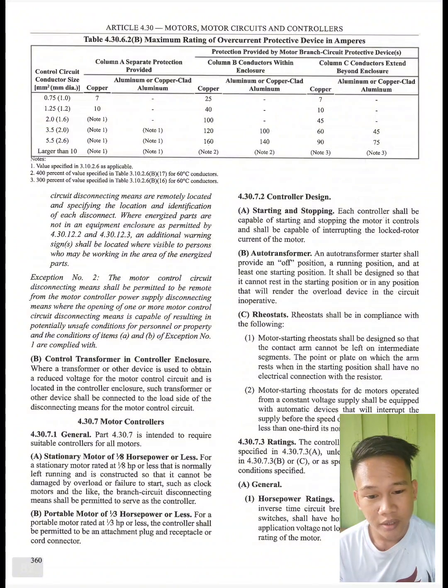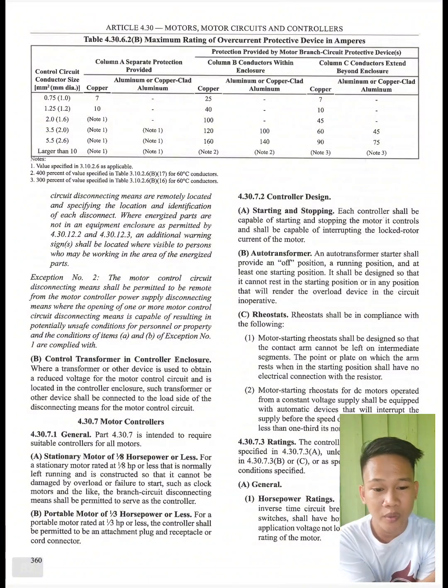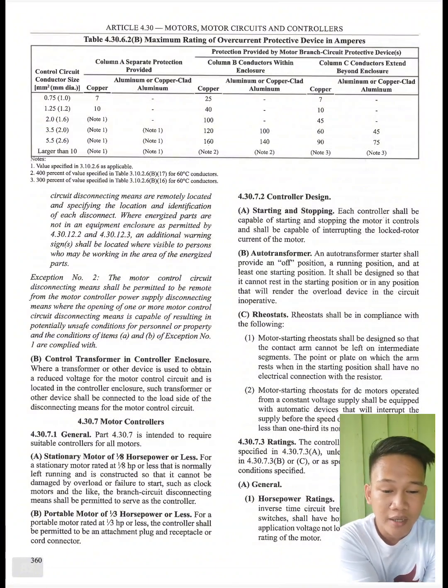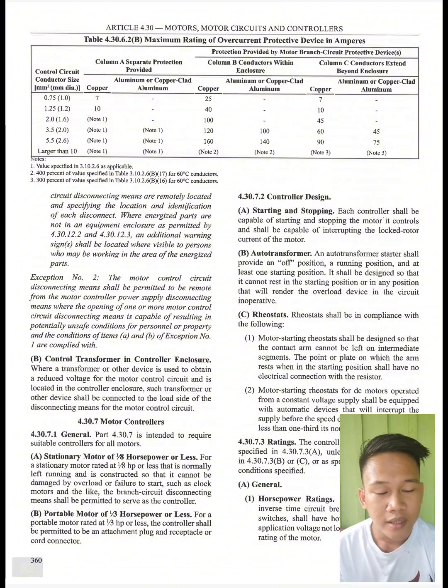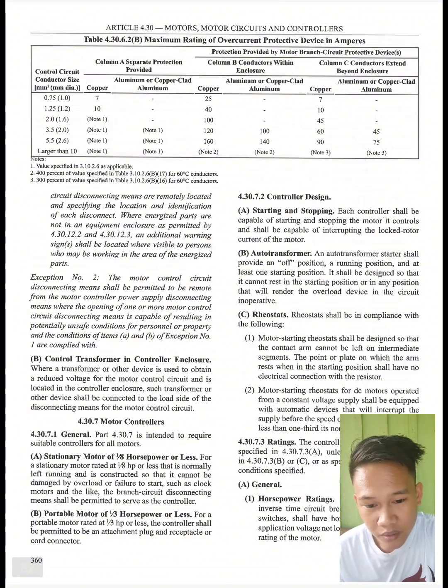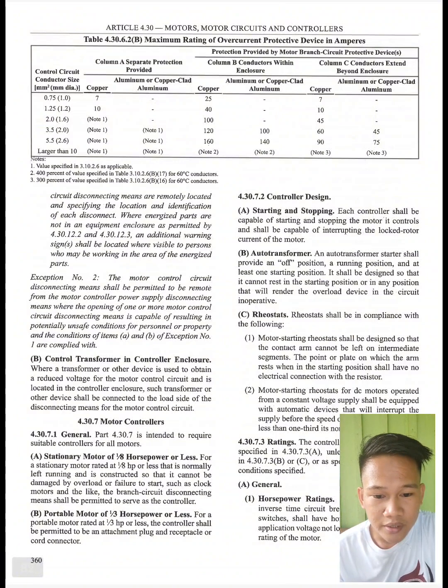So for larger than 10, column A is in note 1, also for aluminum or copper clad. Then in column B, the copper or the aluminum is in note 2. Then in column C, the copper or the aluminum or copper clad aluminum is in note 3. So next is B.